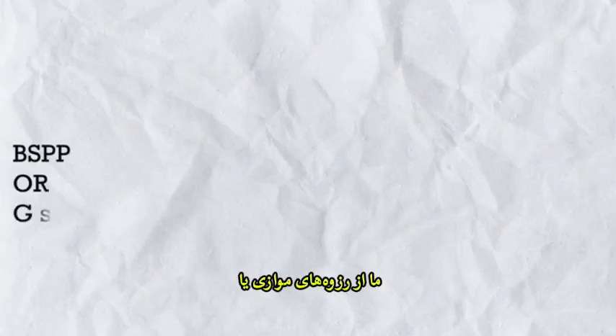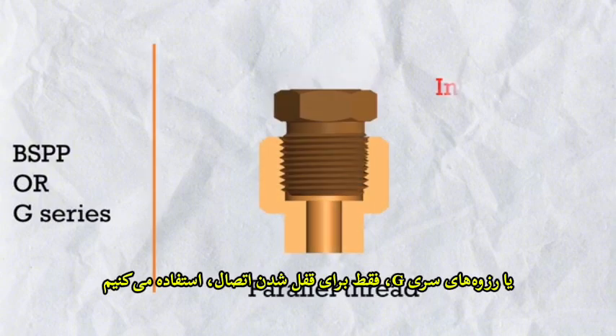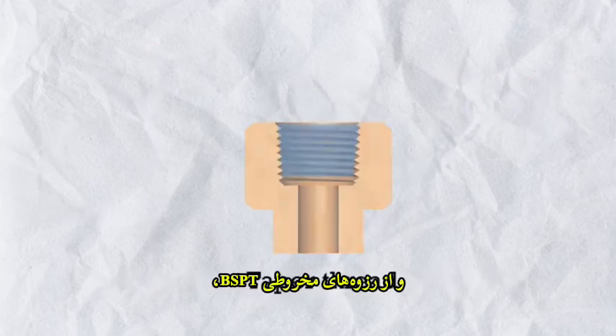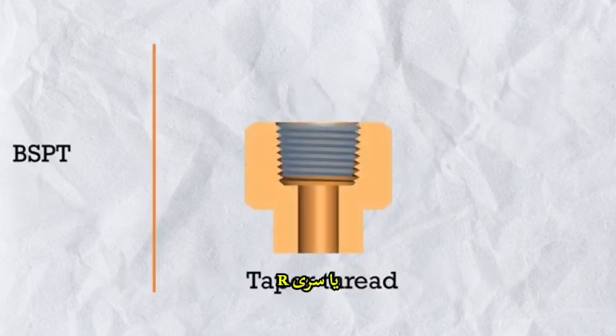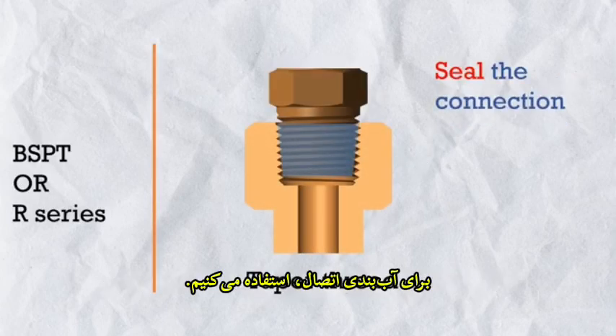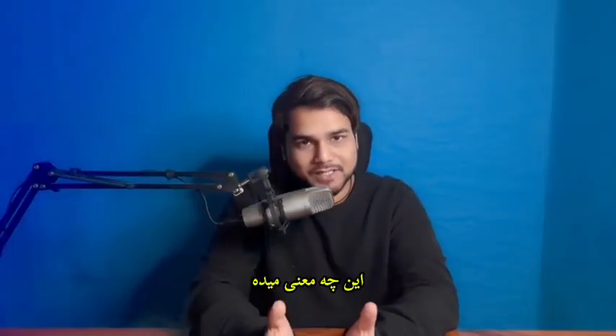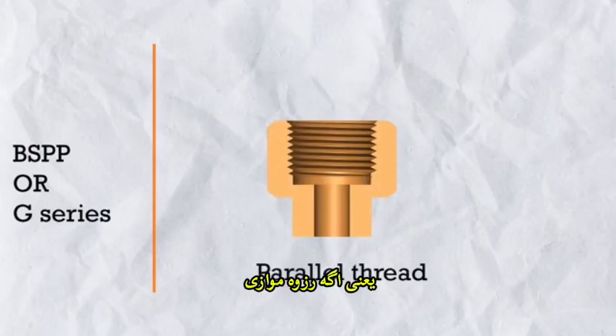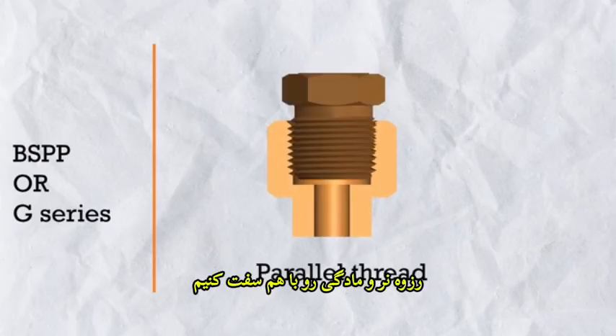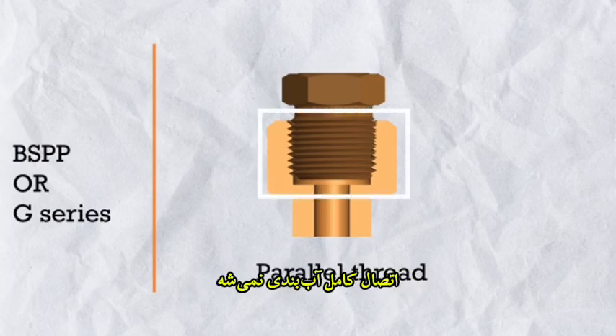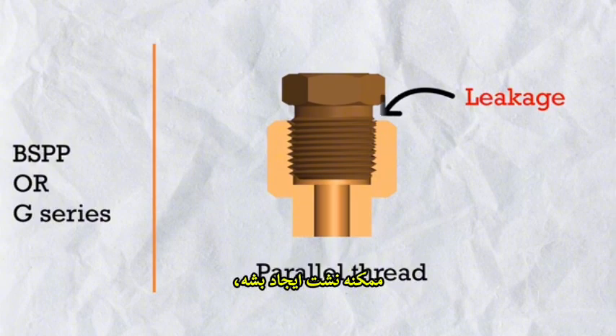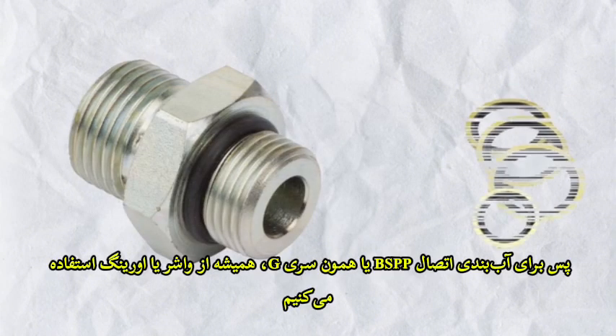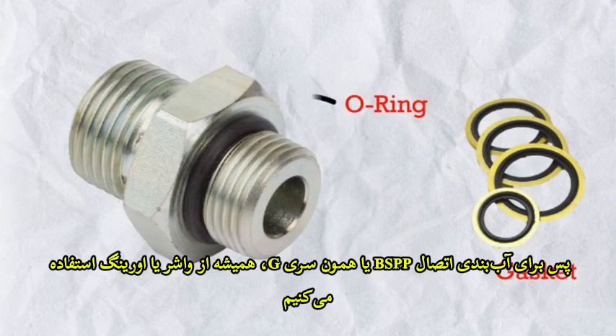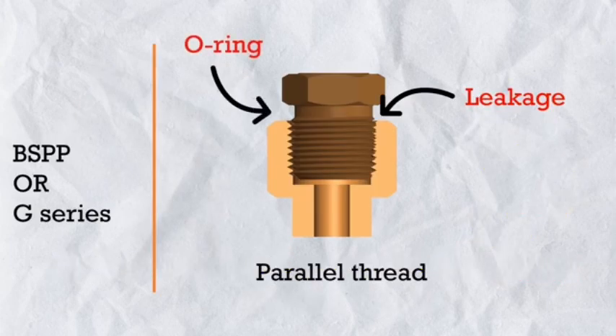So we use parallel threads, BSPP or G series thread, to just interlock the connection, and we use taper thread, BSPT or R series thread, to seal the connection. What does it mean? It means if we tighten the parallel male and female thread together, the connection will not be completely sealed. There will be a leakage. So to seal the connection, we always use gasket or O-ring with BSPP or G thread series.